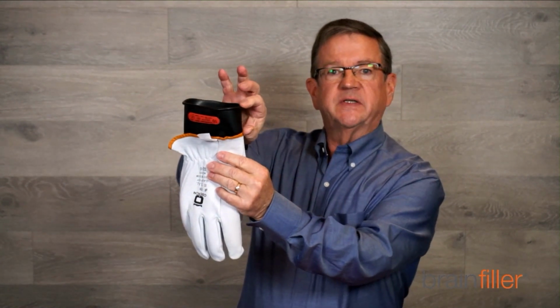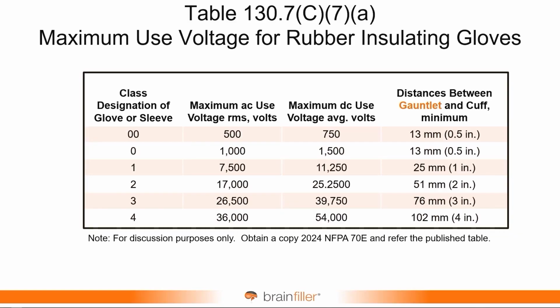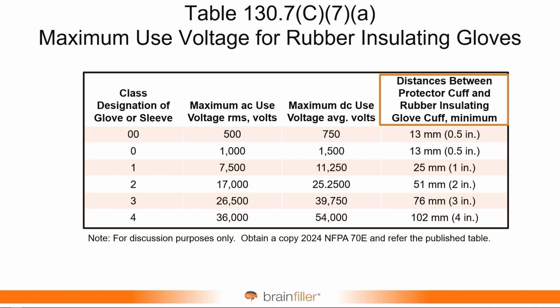It's important that you have a certain distance, and those are defined in a table. Otherwise, if the glove was shorter than the protector, you wouldn't know where your electrical protection ends. Like, I don't know if it ends here or if it ends here or where that is. So there's a certain distance that has to be visible right here. The term gauntlet was used for that, which is a little confusing. Some may just know the gauntlet as, oh, throw down the gauntlet. That's probably the way most people are familiar with this term being used. But this table was modified. Distance between gauntlet and cuff was changed to make it a little clearer: distance between the protector cuff and the rubber insulating glove cuff. So it's just a change in the way it's described up here.